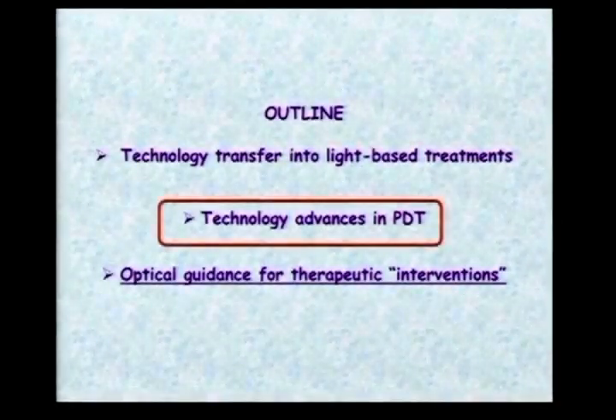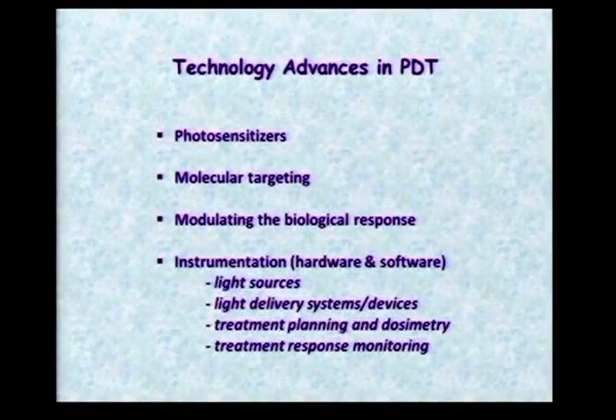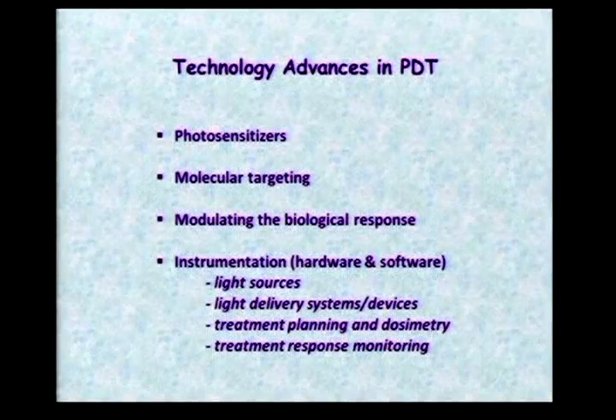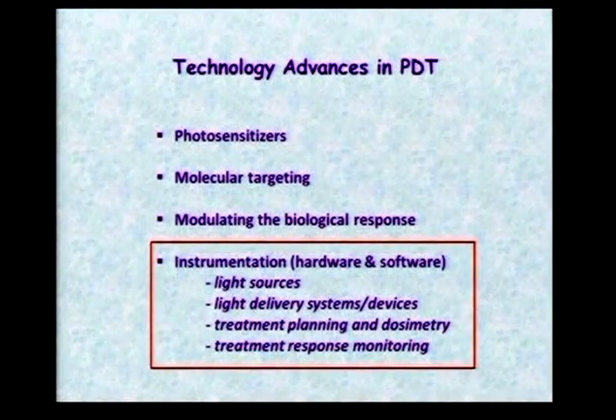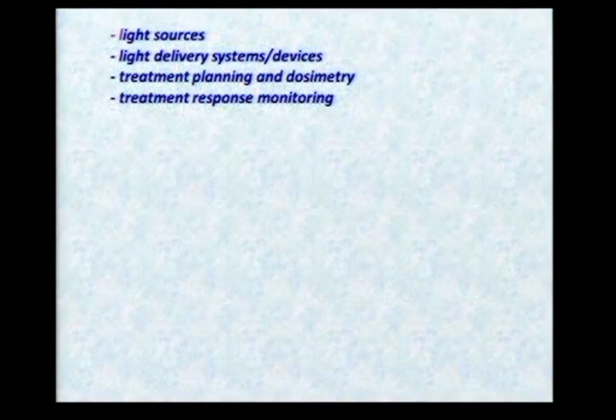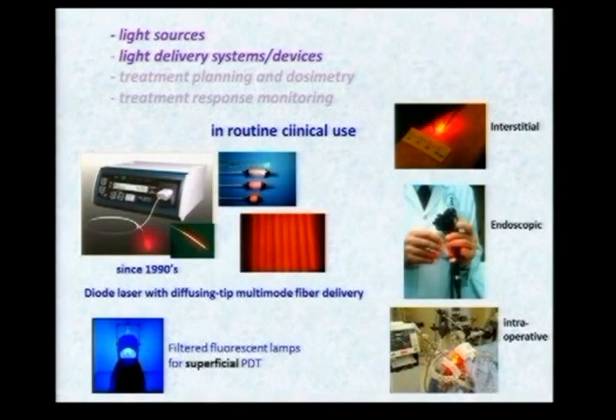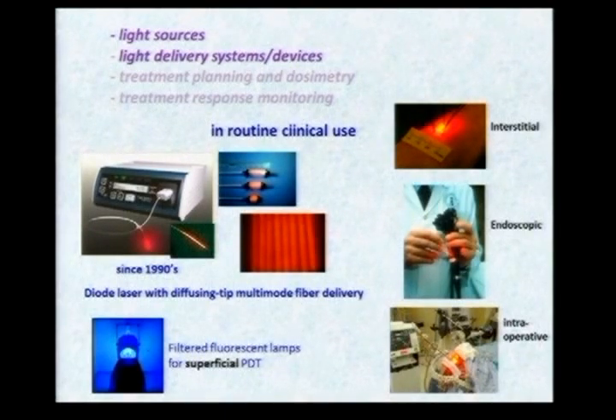Switching now to PDT — throughout this meeting you've heard about technology advances in photosensitizers, targeting, and modulating biological response. Here I want to quickly summarize instrumentation aspects, both hardware and software: sources, delivery systems and devices, treatment planning, dosimetry, and response monitoring — each of which could be a whole course. We've heard about different light sources and delivery systems, and these examples show how you select the light source and delivery system to be optimum for a particular treatment, whether interstitial, endoscopic, intraoperative, or superficial.